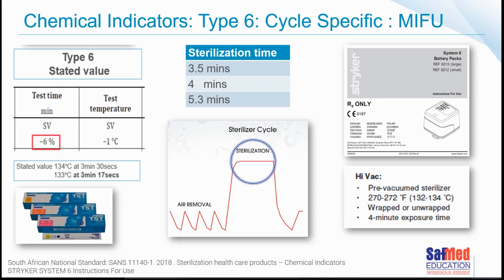I remember at one point, if I remember correctly, the Netcare group had decided that they would standardize their sterilization time at 4 minutes across the group to cover all of these angles and make sure that they got the correct sterilization parameters. Please go back, look, ask for the instructions for use. Try to get them for your loan sets because they are quite clear and quite specific. If you're not doing that, you're not necessarily getting the sterilization time that is required for the devices that you're sterilizing.